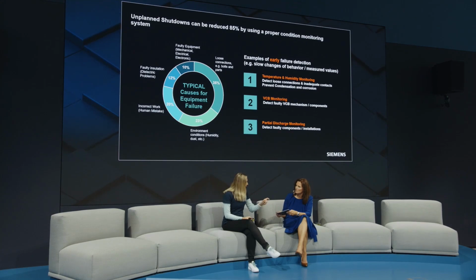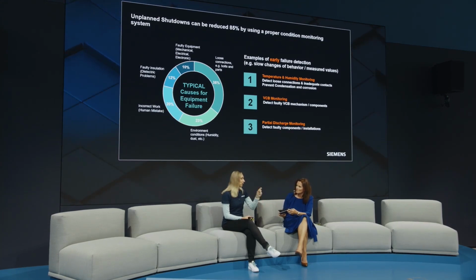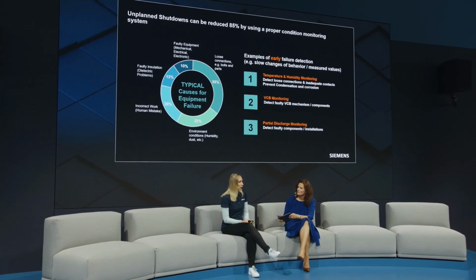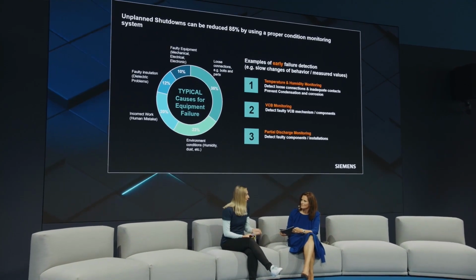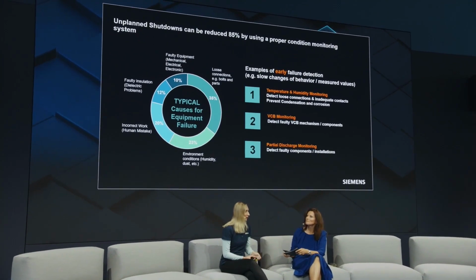The first is temperature and humidity monitoring. With that we can exactly find these failures, remember the failures of loose connection, because we monitor the temperature directly at the cable connections, for example.